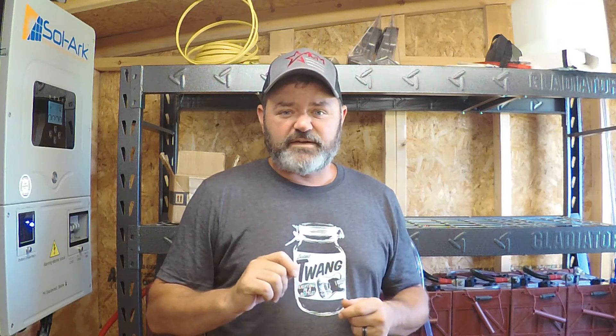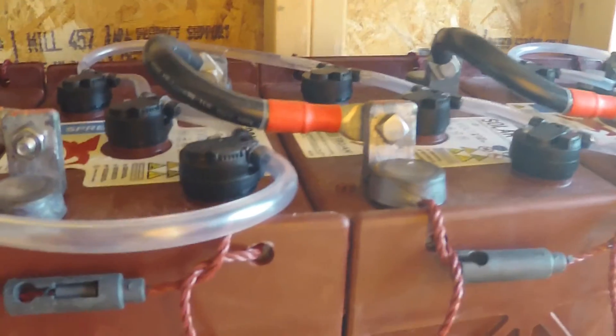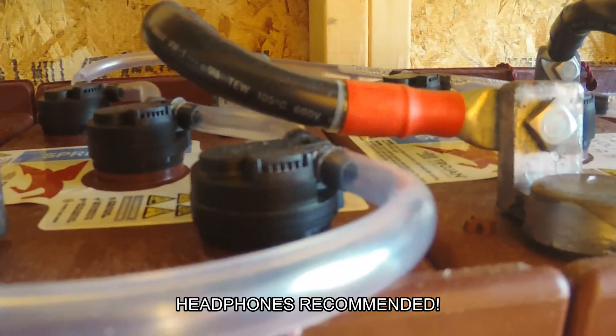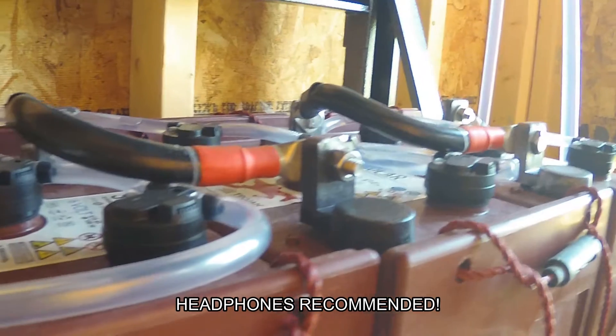Right here we've got an equalization in process. I'm going to be quiet and let you listen — you'll actually be able to hear the batteries boiling inside. As you can see on the Sol-Ark, our battery voltage is currently 61.2 volts. Batteries are typically 48 volts, so we are definitely in the middle of an equalization process.